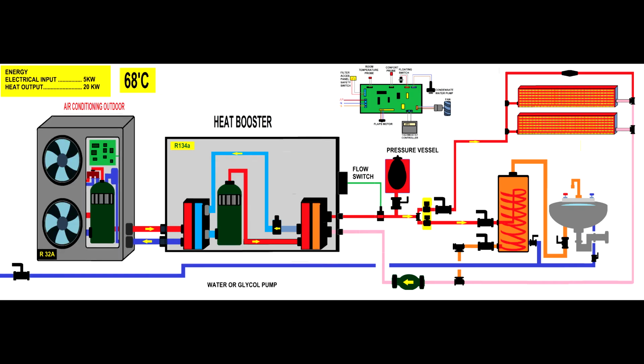So I have the outdoor on R32A refrigerant, and some of them run on R134A outside, but in winter they will not be efficient at all. So I'm using R32A outside, then the heat booster will be R134A, and R134A will heat the water. I fitted a flow switch onto this water circuit to make sure that if the water is not circulating, the heat pump will not run. I don't want to overheat the refrigerant and to increase the pressure in the system.